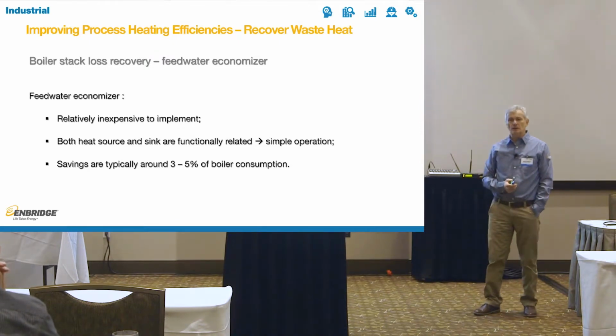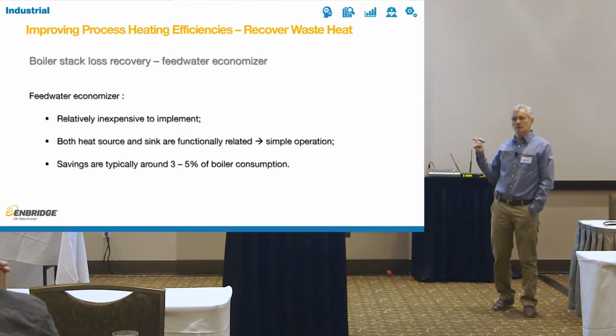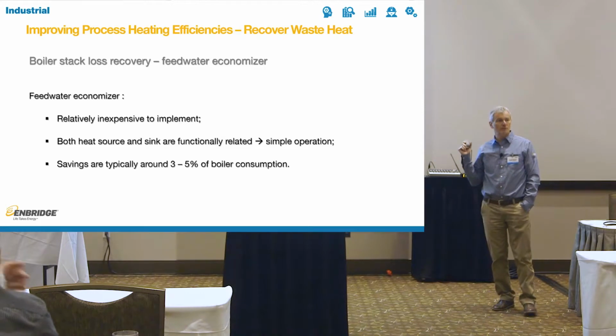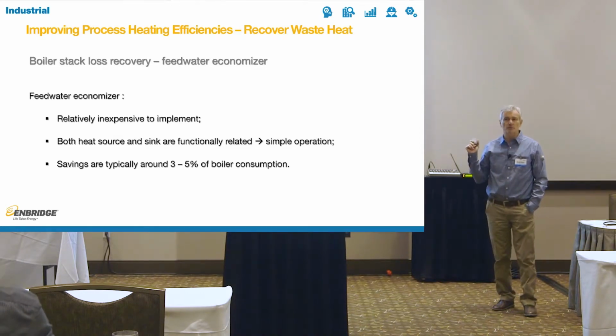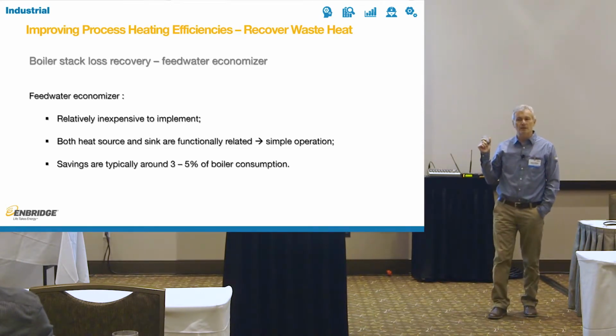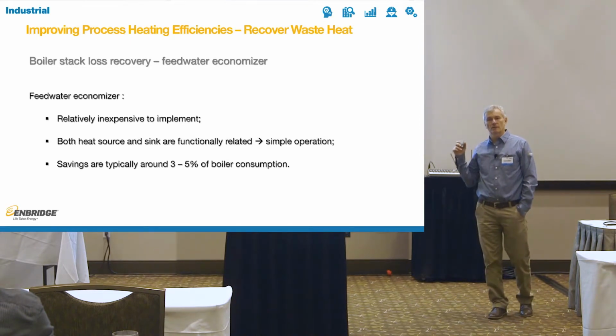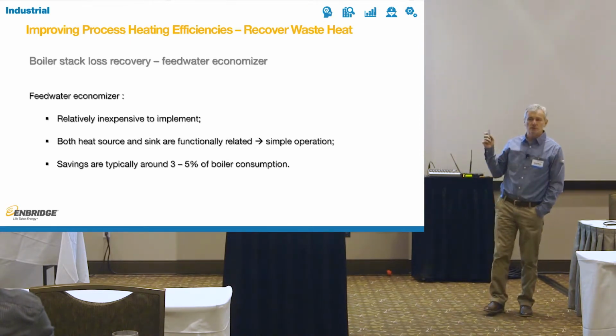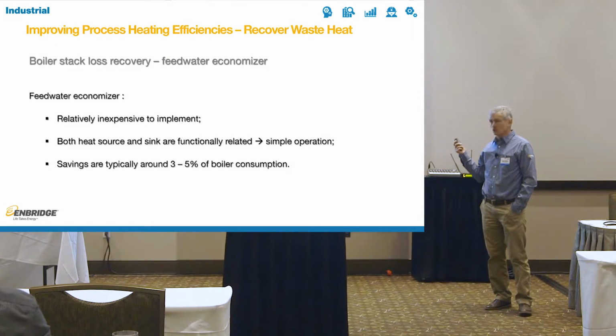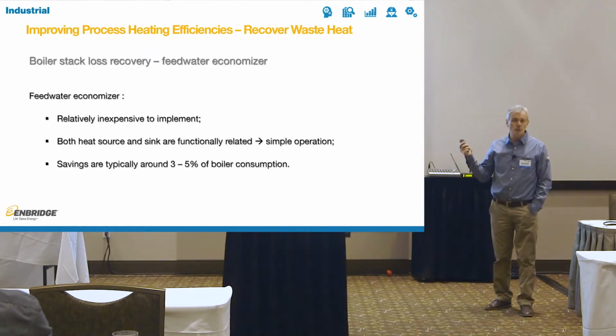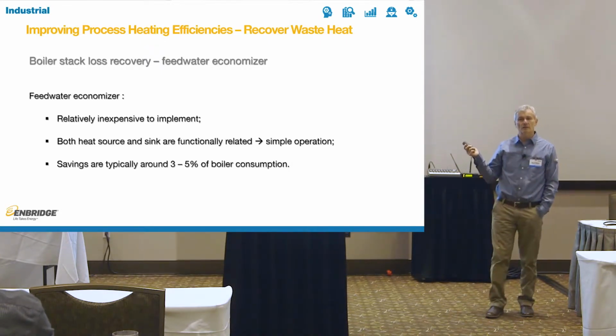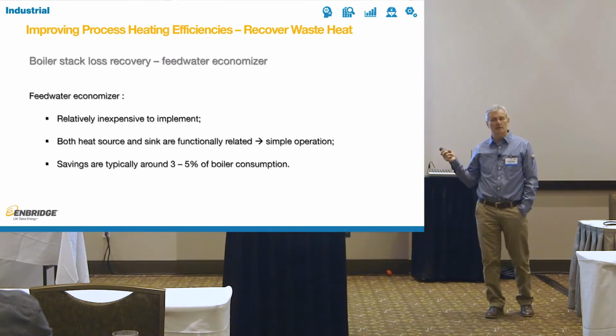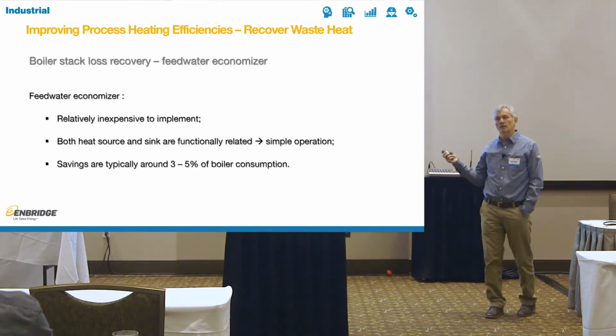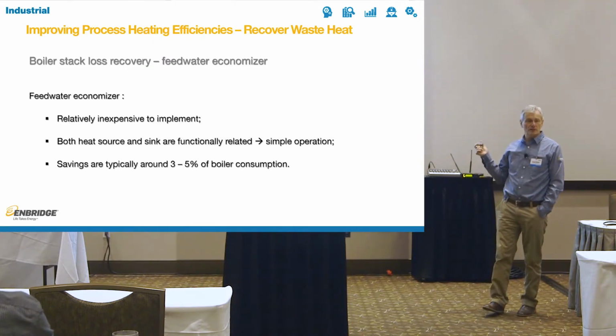Savings are typically around 3 to 5%. If anybody tells you that they're going to save you more than 5% with the Feedwater Economizer, call us before you spend the money, please. They are probably deluding themselves, so I would not trust it. It's usually 3 to 5%. 5% is on the high side; 3% is more likely. So if anything goes out of those numbers for a Feedwater Economizer, question it.